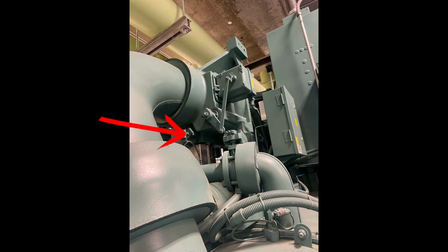So we want to make sure that where the arm, or the shaft, for the guide vanes is positioned is at a fully closed point. That way it matches fully closed at the vanes and fully closed at the actuator. And you want to make sure you also put a little bit of pressure on it. Not hard, like you're forcing it, because then you'll end up putting too much stress on the vanes themselves. But you want to make sure that it's solidly closed, because if you don't get this part right, the vanes may allow too much leakage through them at startup, which is going to cause your motor to go into an overcurrent because the vanes aren't fully closed properly.